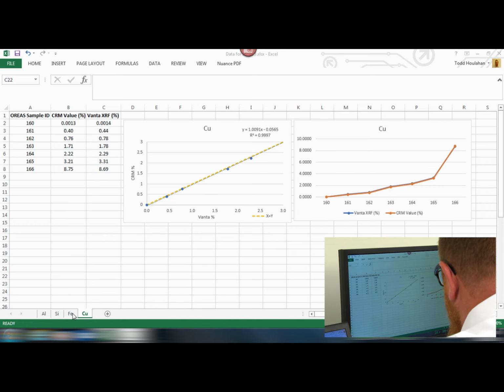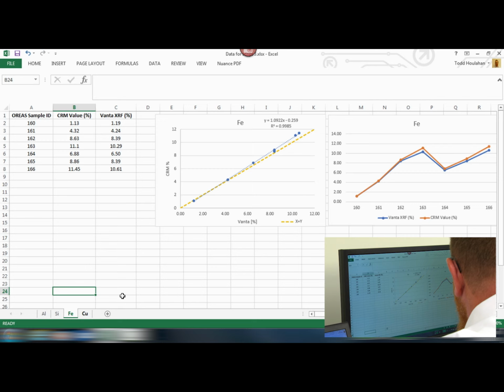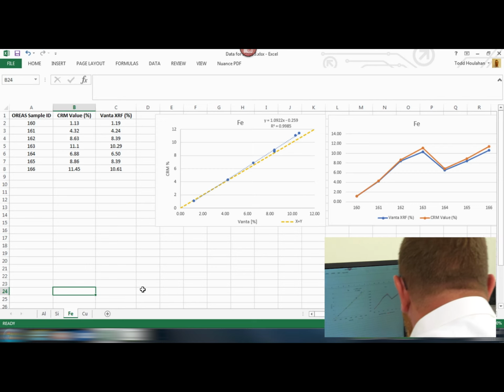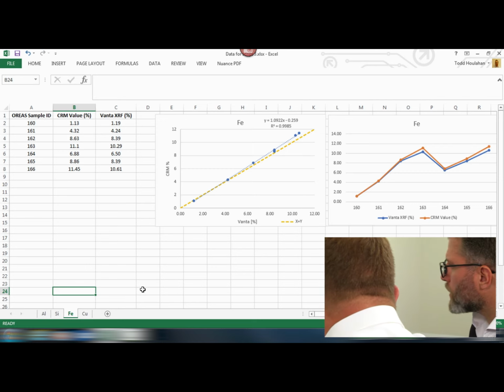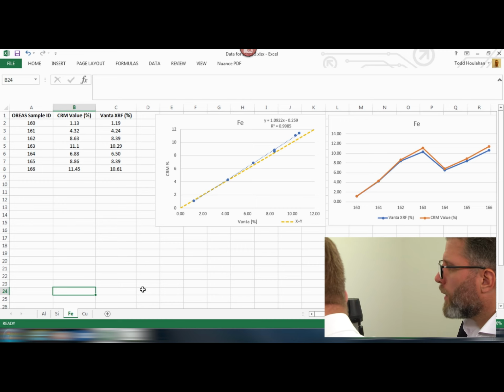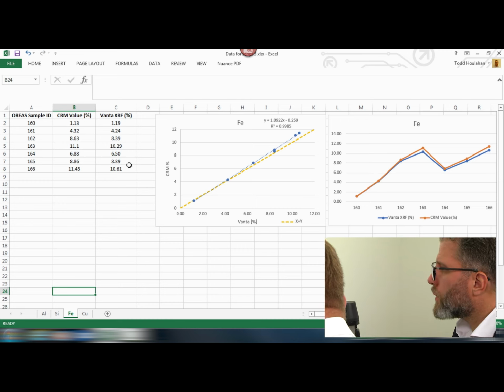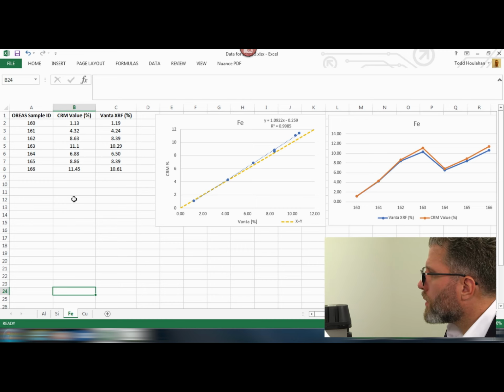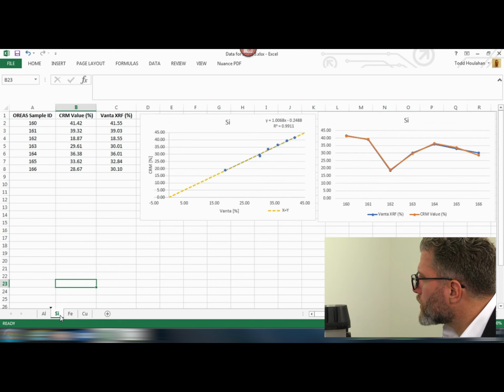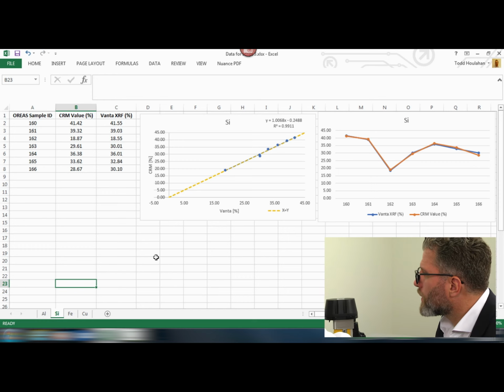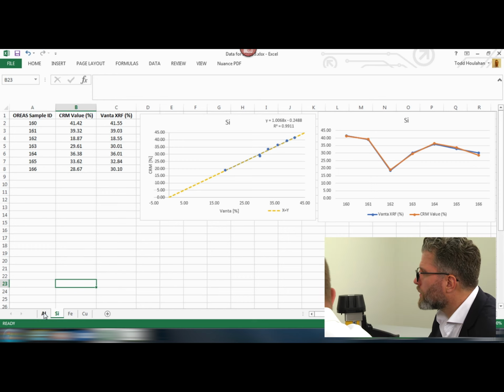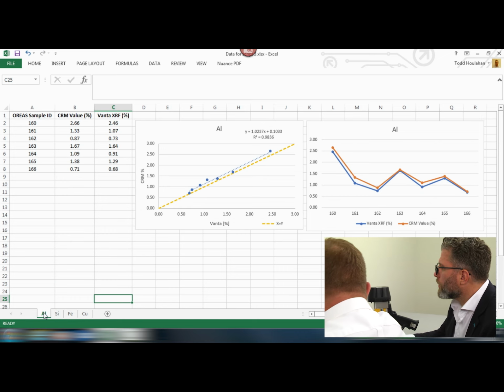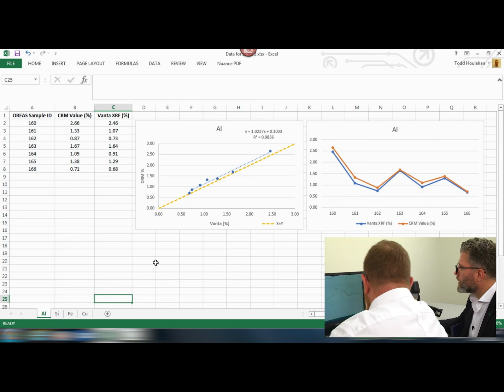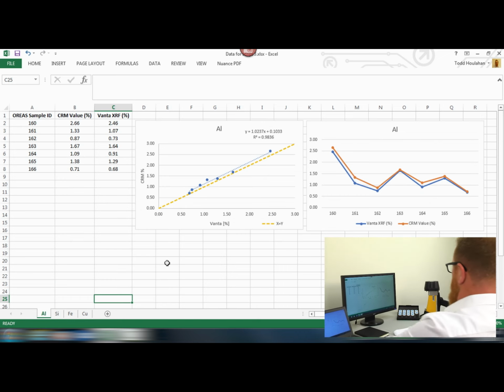Let's look at iron. Iron looks pretty good too. It's reporting a bit low at higher concentrations, it seems there, Todd. Yeah. There's the certified values versus the XRF factory calibration. But the trending still looks good. Silica. Silica's fabulous. Wow, out of the box. Pretty impressive. Aluminium. Wow, look at that aluminium. Again, the trending looks great. Reporting a little bit lower. Yeah, a little bit lower across all concentrations.